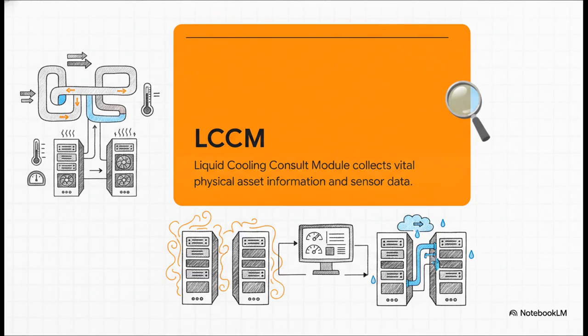So SCC includes the Liquid Cooling Consult Module, or LCCM. This system collects and analyzes vital physical asset data straight from your CDU, the cooling distribution unit. We're talking real-time sensor metrics on coolant temperatures, flow rates, pressure, humidity, and even the status of individual pumps and valves. It actually manages both your air-cooled and liquid-cooled servers within the exact same interface, making sure your hybrid infrastructure is running as cost-effectively as possible.